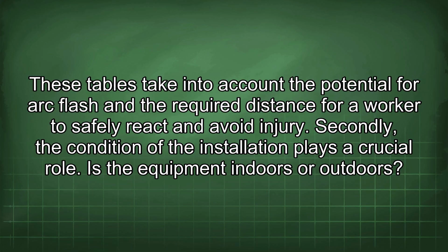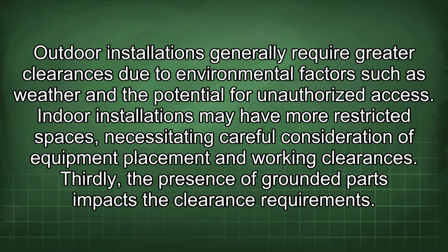Secondly, the condition of the installation plays a crucial role. Is the equipment indoors or outdoors? Outdoor installations generally require greater clearances due to environmental factors such as weather and the potential for unauthorized access. Indoor installations may have more restricted spaces, necessitating careful consideration of equipment placement and working clearances. Thirdly, the presence of grounded parts impacts the clearance requirements.